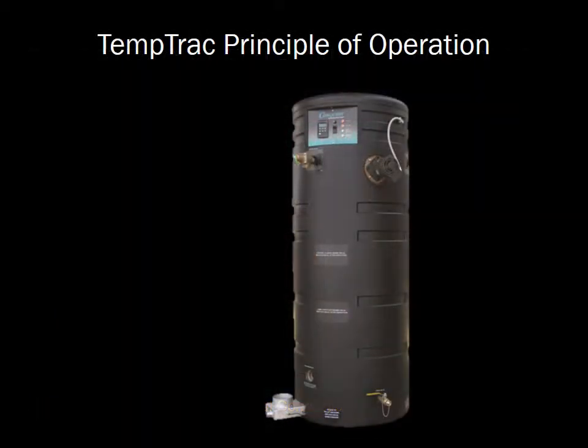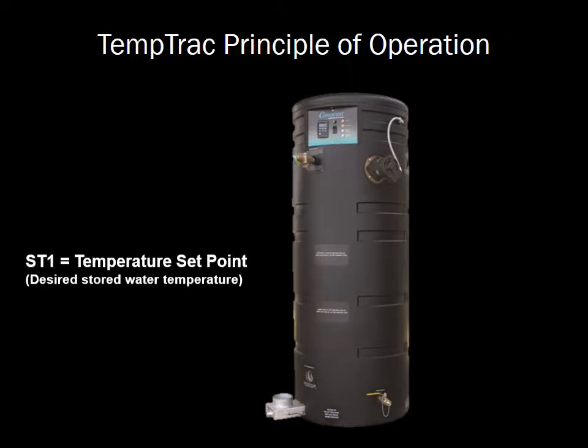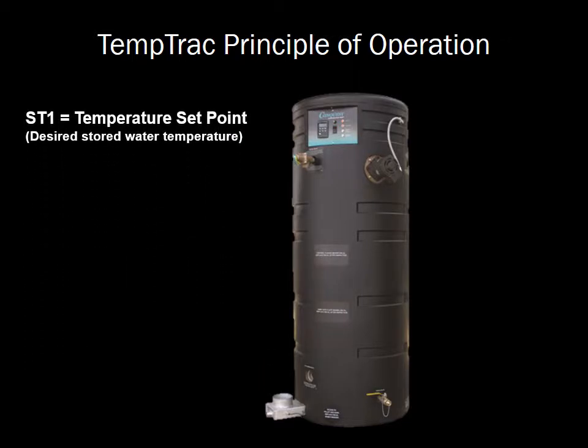The water heater operates to satisfy the stored water temperature set point of the Temptrac operating control. The value of the control set point, ST1, is the desired stored water temperature. The unit ships with a factory set point of 120 degrees Fahrenheit. As hot water is consumed from the top of the tank, cooler water enters at the bottom of the tank and the stored temperature begins to drop, thus activating the call for heat sequence of the water heater temperature control system.